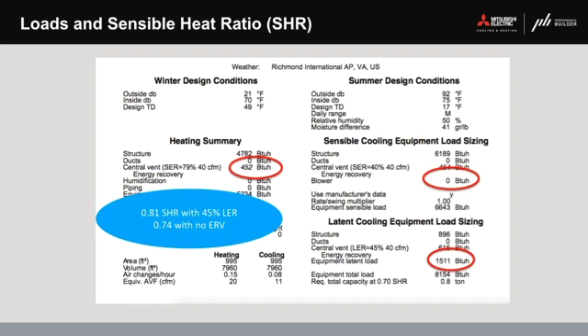And so what we call a sensible heat ratio, which is really just a simple fraction of sensible heat or sensible load over our total load, that number has gone down. Now, some of our higher performing equipment, the SHF or sensible heat fraction, which is really the same thing, has gone up. So we have to make sure that we're tracking the sensible heat ratio of spaces and the sensible heat fraction of equipment in order to make sure that we are specifying equipment that truly meets the needs of these spaces.